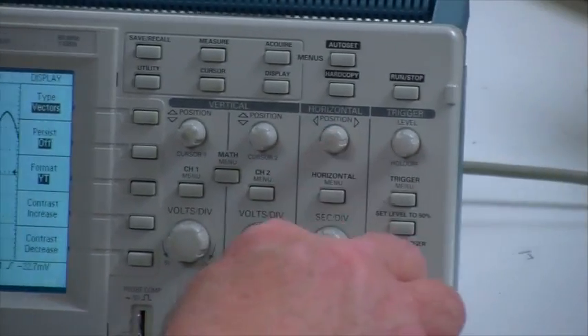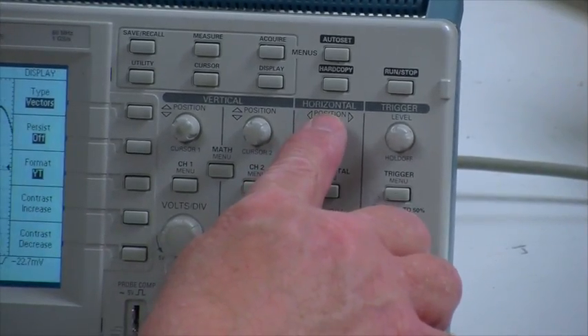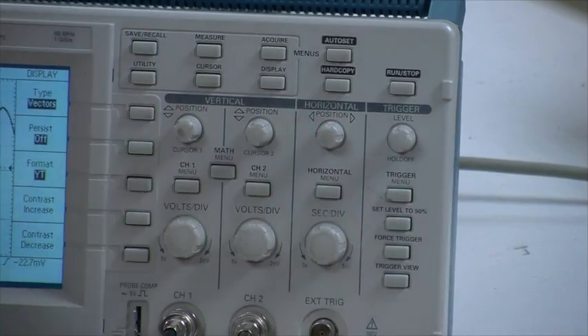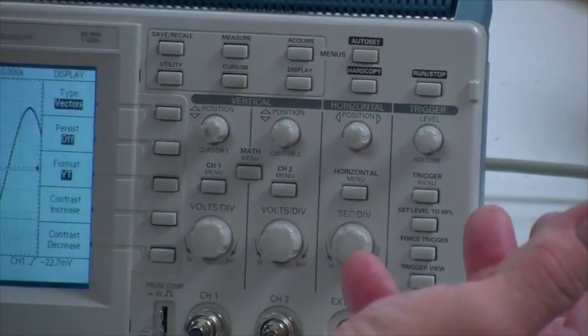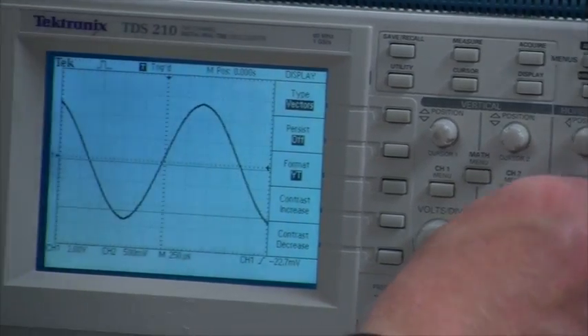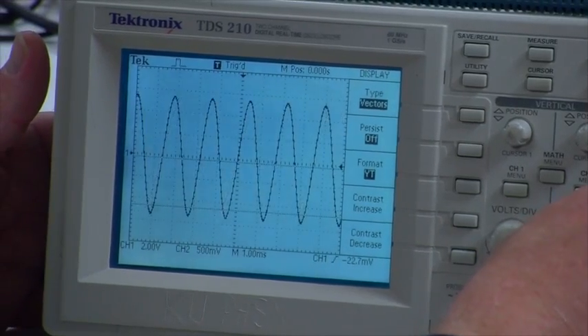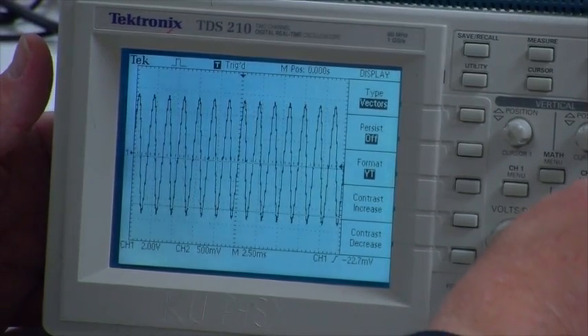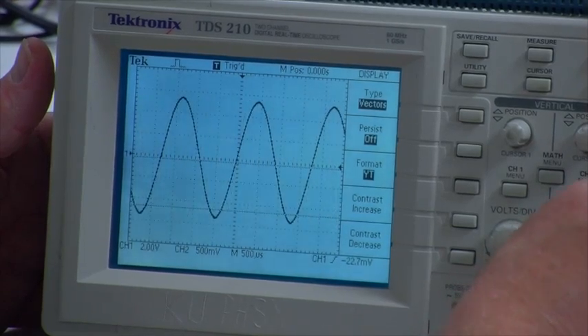This one over here, this set of controls marked horizontal, controls the x-axis, which is time. And so when I change the seconds per division, it lets me see more cycles or fewer cycles.